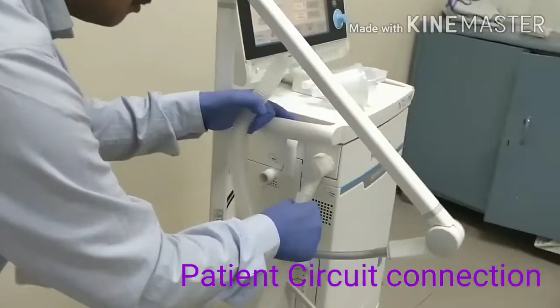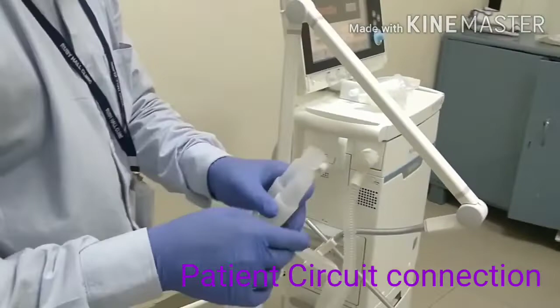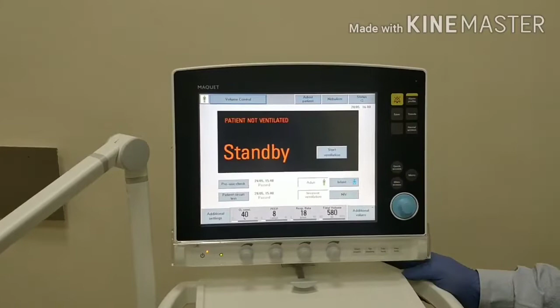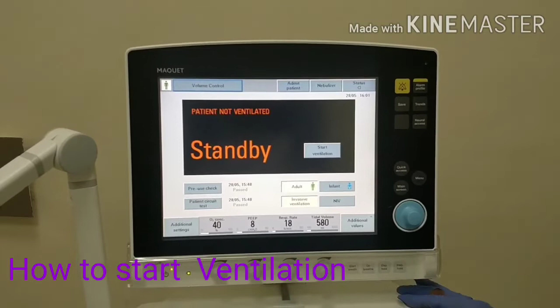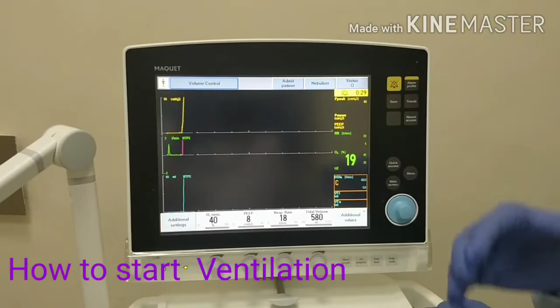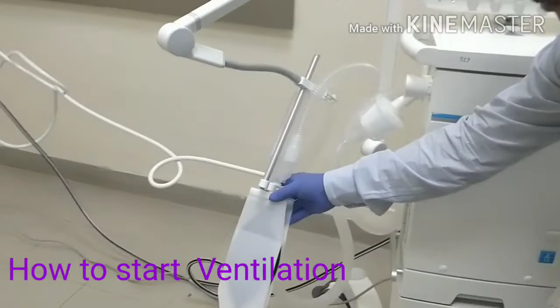This is a disposable patient circuit. Now see how to connect it to the ventilator. This is the expiratory side, this is the inspiratory side, and this end goes to the patient side. So here we are connecting a test lung instead of a patient. After selecting the mode and parameters and connecting the tubing, we have to start ventilation. So this is start ventilation now. Just press it, and your ventilation will start. Here is the test lung. Now it is ventilating.